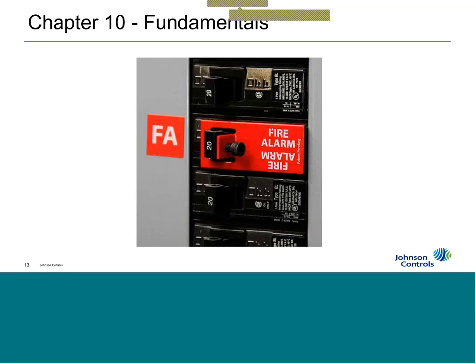One of them is certain areas of the United States will use these circuit breakers as light switches, and they will go in every morning and every evening to turn on and off the lights in various areas. Now, I know the electrical code says you're not supposed to do that, but some of these government entities, and I can give you several examples of where they are in the U.S., do this routinely. The unions require that only the person the union authorizes can turn the lights on and off, so the cabinets are locked up, and sometimes they turned off the wrong breaker, and then the fire alarm was without power, the batteries died, and then we didn't have a fire alarm system.